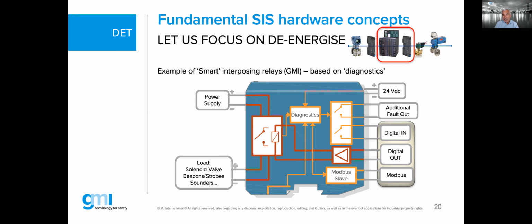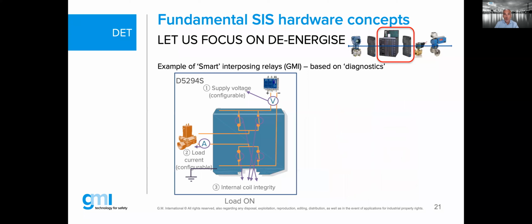So provided that this smart relay is somewhere in between your control, let's say safety PLC, or let's say your BPCS system, towards the final elements, you can feed this signal back into your control platform to say something is wrong in the field. It may be a short circuit, it can be an over voltage, it can be an under voltage, whatever the reason could be. That can be fed back into the diagnostics to your control platform.